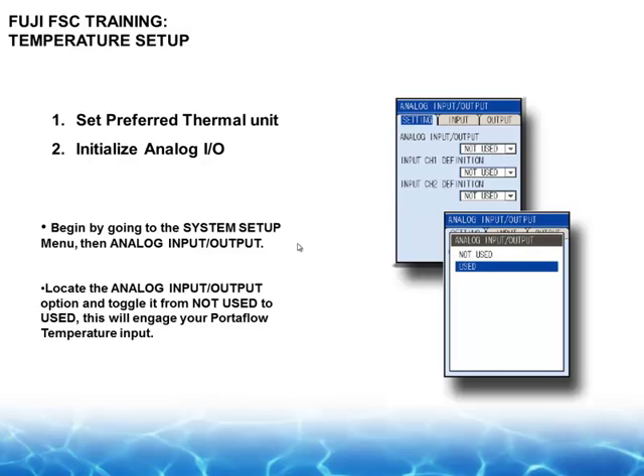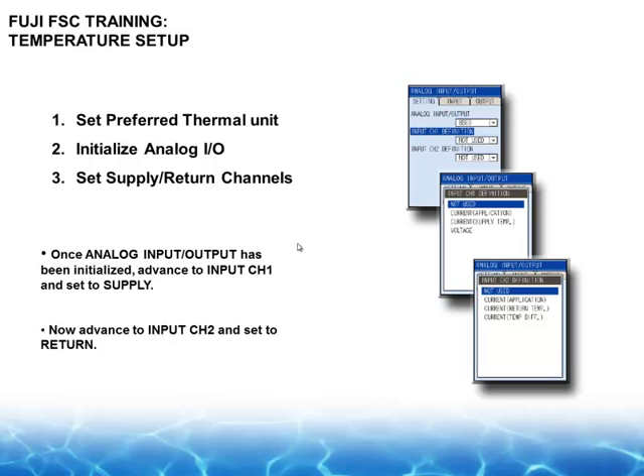So before you go to the System Setup menu, we need to take a look at the analog input and output. So locate the analog input and output and toggle it from not used to use, and this will engage your Portaflow temperature input. Once the analog input output has been initialized, now we advance to input channel 1 to set a supply. So as I said before, this collects all the data, so when your end user looks at this, the chart will say temperature 1 is the supply line and temperature 2 is return line.